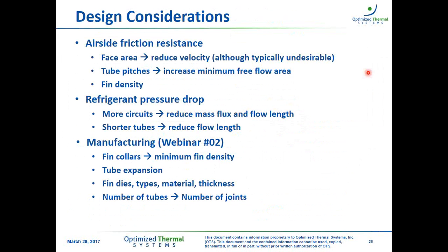Another way is finding tube pitches that increase the minimum free flow area or reduce the flow acceleration inside the tube bundle that can increase the pressure drop as well. And we can play around with the fin density also to reduce the actual surface that is going to pose additional resistance. On the refrigerant side, one way to do so on tube fin heat exchangers is to have more circuits. Having more circuits, we have reduced mass fluxes and overall flow length, overall path of the refrigerant, or even having shorter tubes, if that's the case.